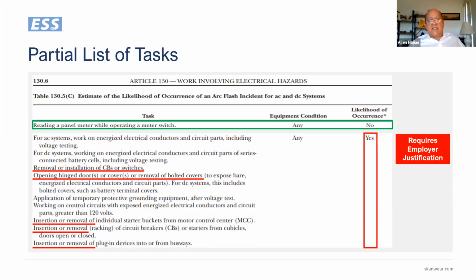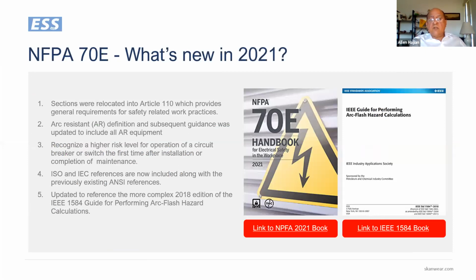But for all the other tasks in the table, and I've underlined some of the common tasks I've seen performed in an energized state: removal or installation of circuit breakers or switches. That requires employer justification. Why are you doing that in an energized state? Opening hinged covers or removal of bolted covers, insertion or removal of buckets, insertion or removal of breakers, insertion or removal of plug-in devices into busway. All of those are energized work with the likelihood of injury to the person performing the work, so the employer needs to justify why it's required. If you take anything away from this, make sure you know what the employees are doing and why they're doing it, and whether you take responsibility for that task.